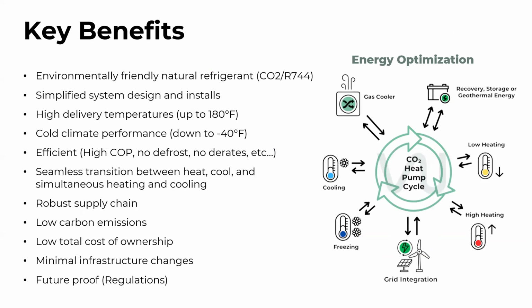Without going too deep, we've built a system that can be an energy engine in the middle of all this - we can do low temperature heating, high temperature heating, cooling systems, whether high temperature sensible only, low temperature comfort cooling, low dew point, or even freezing applications, all with the same product. We can engage energy recovery, energy storage, and geothermal energy, and seamlessly transition to an airside source or sink. This system is also ultra responsive because it's a little mini central plant in a box that can make grid integration possible. Ron's going to talk about that in a moment, but there's a lot of potential there.